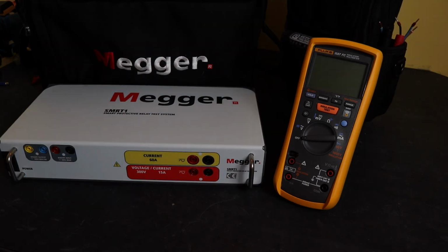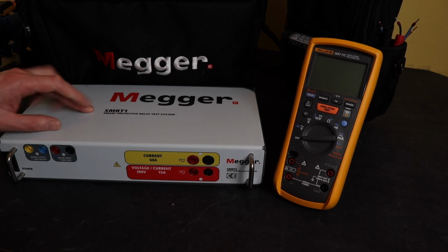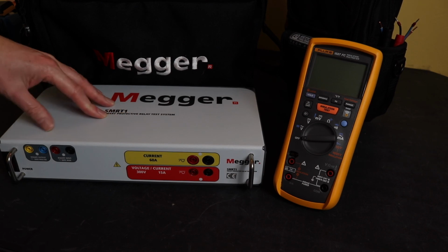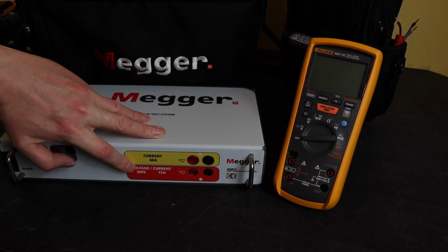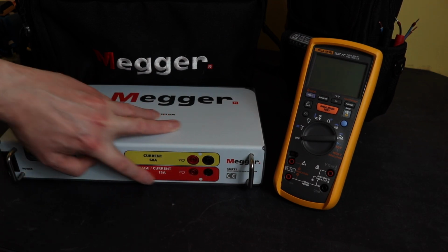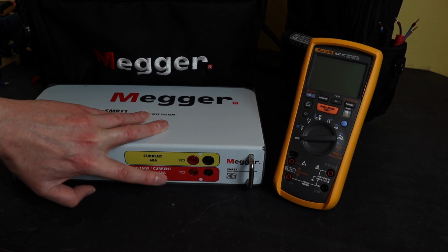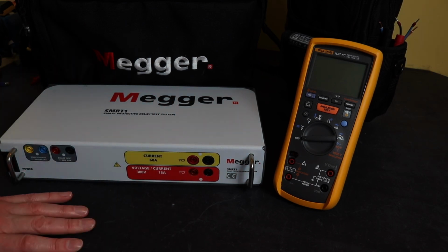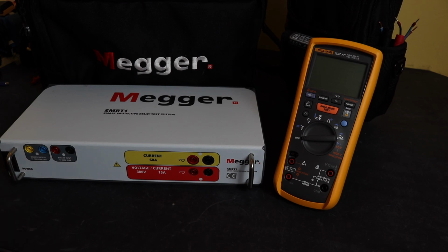For me, the way I could really improve this setup is if Megger came out, adapted one of these units specifically for transducer measurement. So they've got the current capability. Actually, in this 1 voltage module that they have here, it also has current capability up to 15 amps, which is fine for transducer testing for me. So just a unit with one of those modules in there, and then instead of having binary inputs, if they had an analog input to a specific program to do the ramp and measure 4 to 20 milliamps or 0 to 10 volts, whatever you require, that would be the way I would get a good improvement over using this setup that I've got. But currently, at this moment in time, other than going to the huge Omicron, which is a pain to carry around, this is the best setup that I've got at this moment in time for testing transducers out in the field.